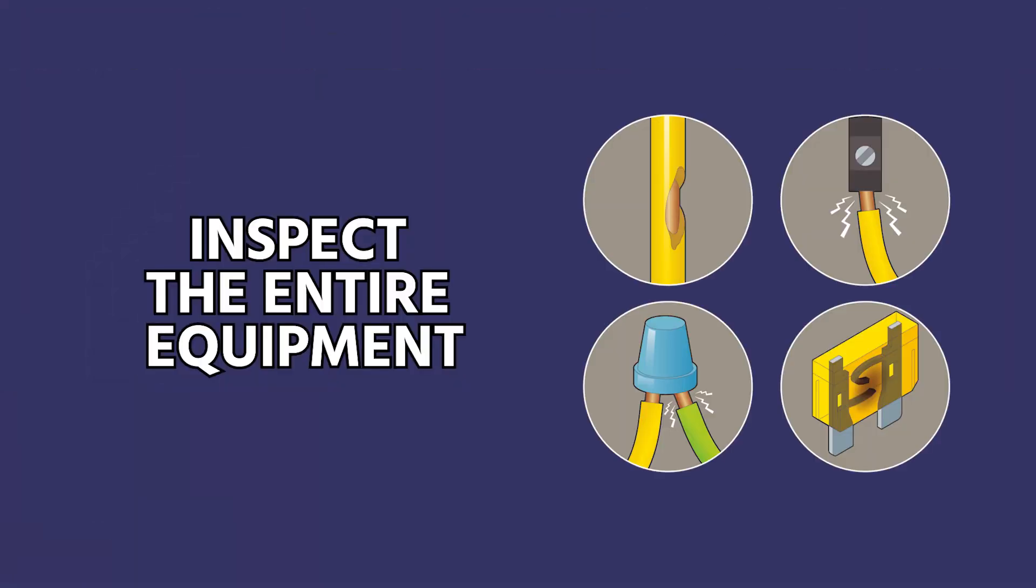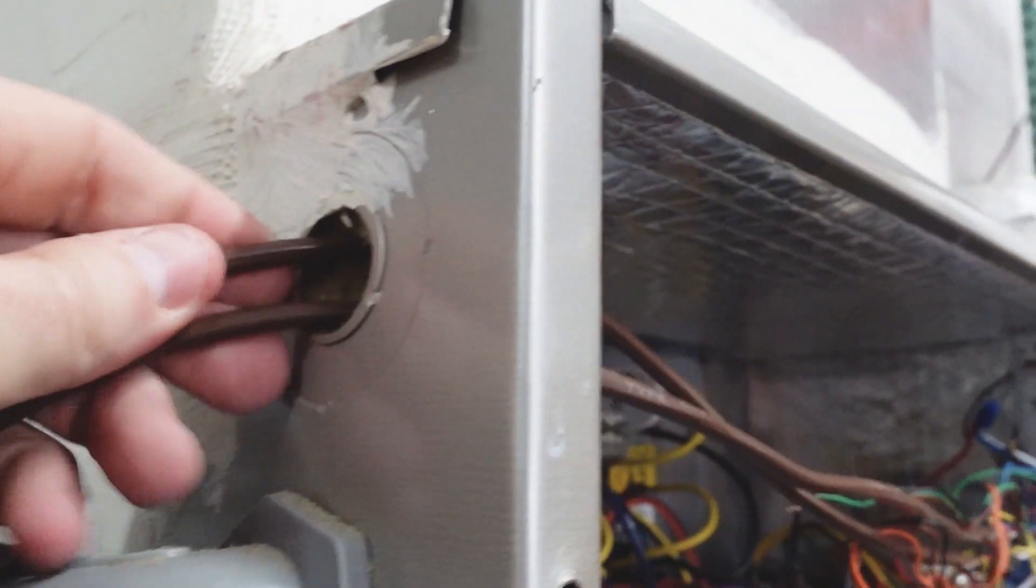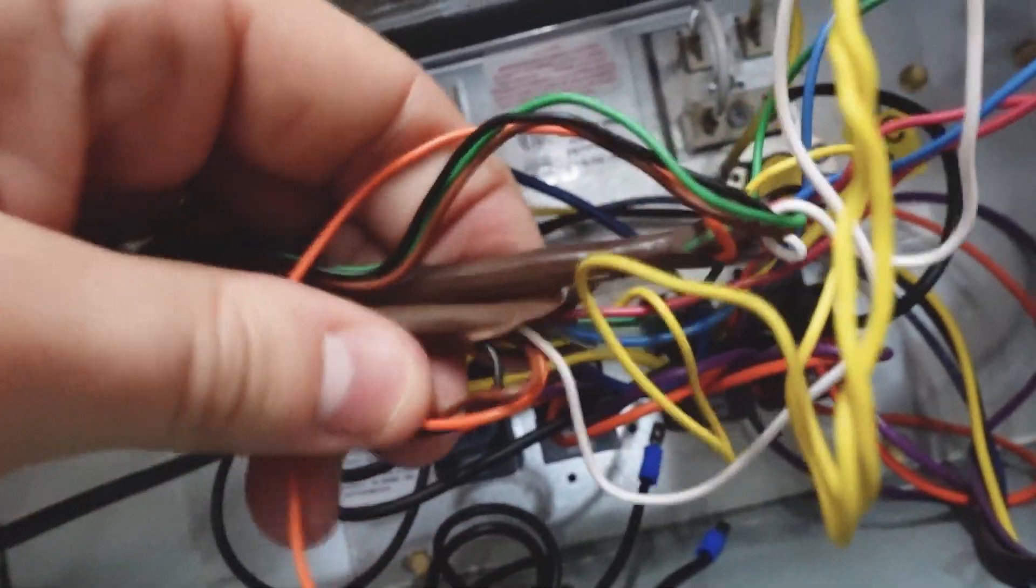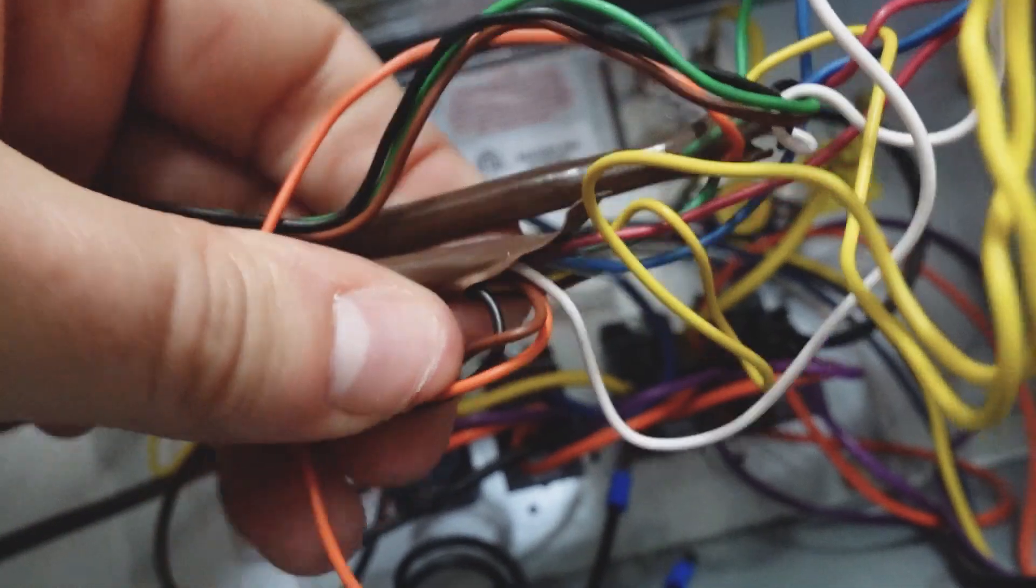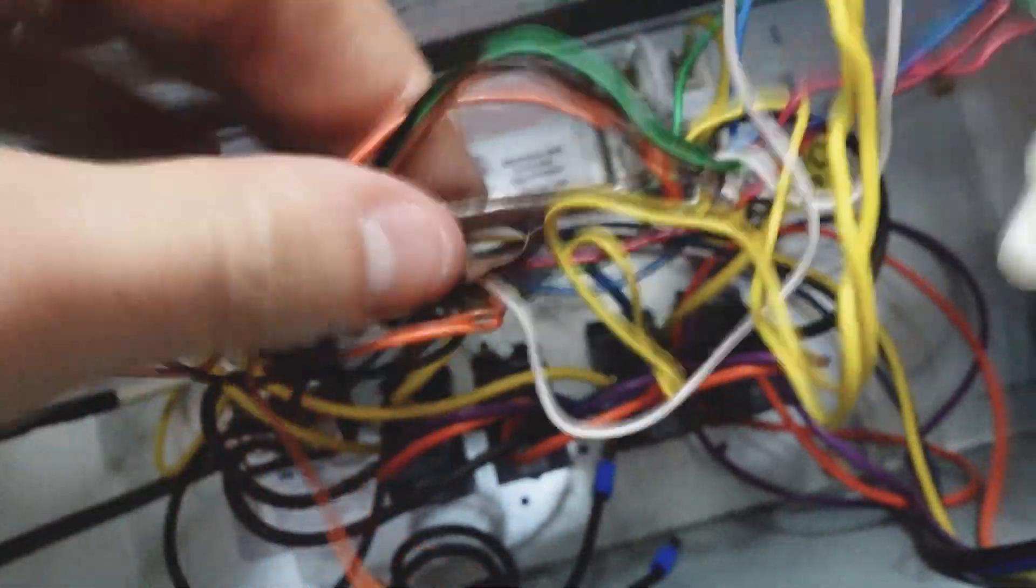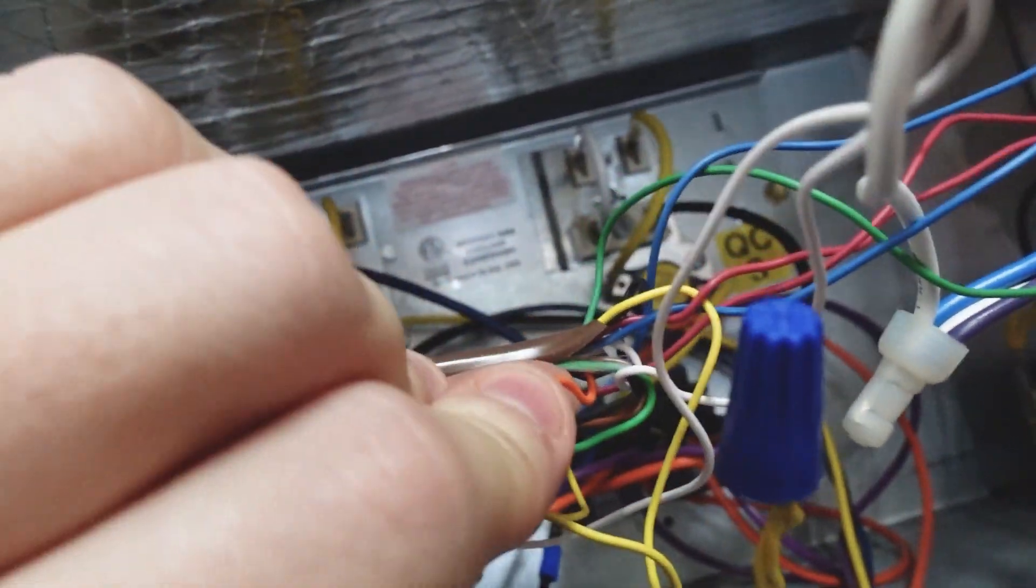When a system has a blown fuse, you want to pay attention to all the connectors and anywhere that the wires are moving through the cabinet. You can see here these thermostat wires don't have a proper grommet protecting them. It would be very easy for this sharp metal to damage the jacket, which could cause a short circuit. We'd want to inspect the places that previous technicians stripped back the outer jacket to make sure they didn't ring around the wire and create any nicks.